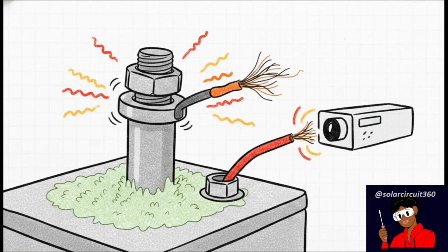Now hold on, before you go ripping out and condemning a cell, you've got to watch out for false symptoms. Things like loose hardware, corrosion, undersized wires, or just poor contact surfaces. These can all generate a ton of heat and added resistance. And that connection resistance creates a voltage loss that perfectly mimics a bad cell. It's a total fakeout. Plus, that excessive heat is going to age your battery much faster. That's exactly why grabbing a thermal camera and physically inspecting all your connections is an absolute must before you start replacing really expensive components.